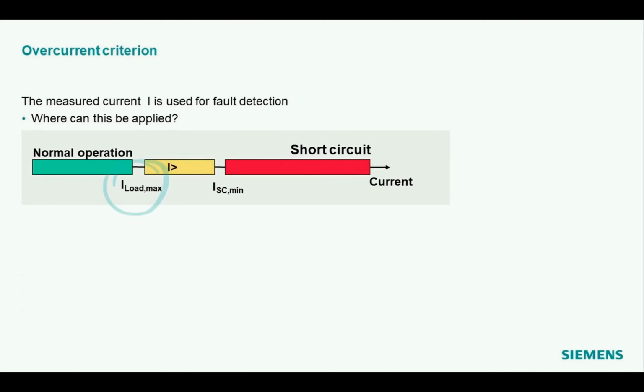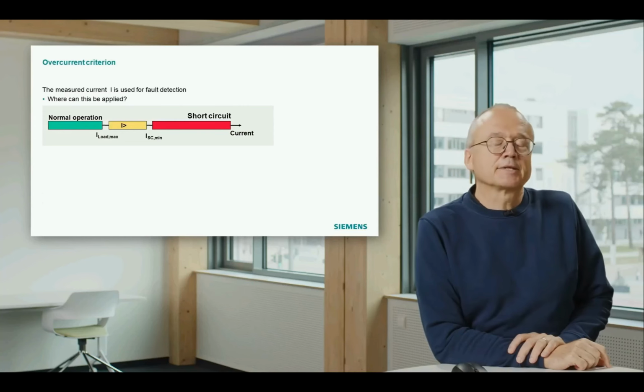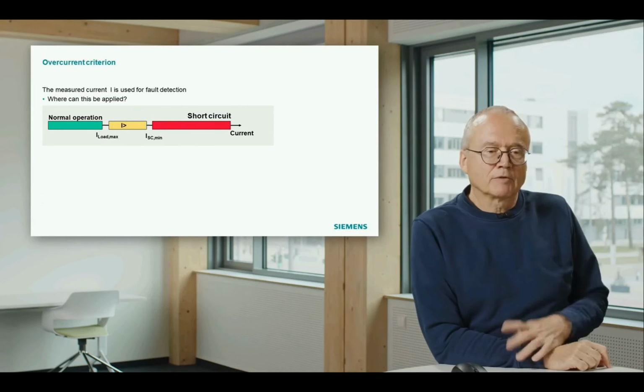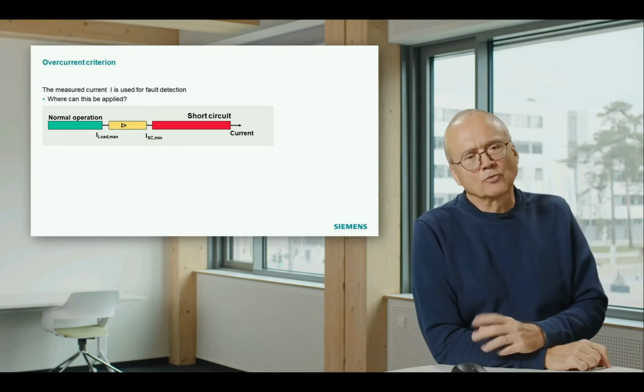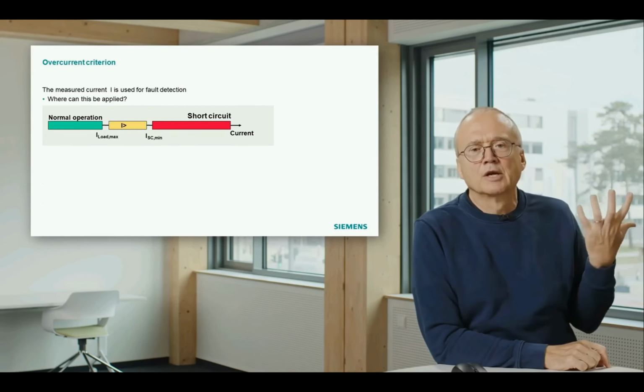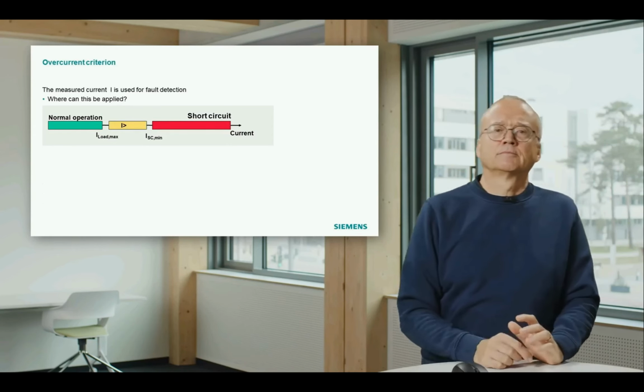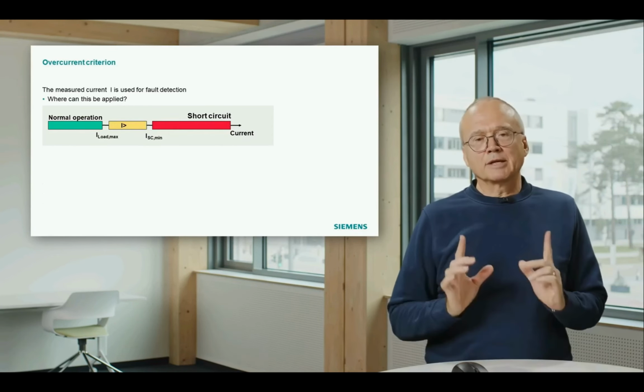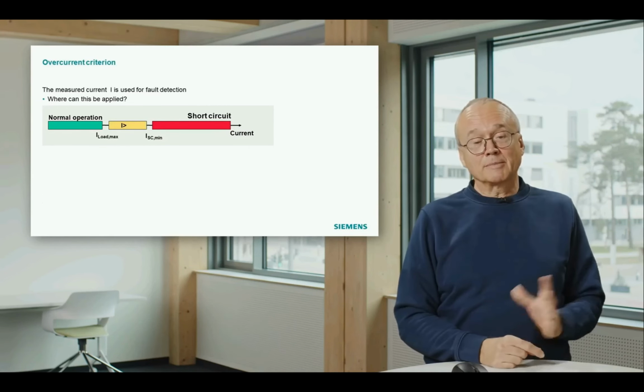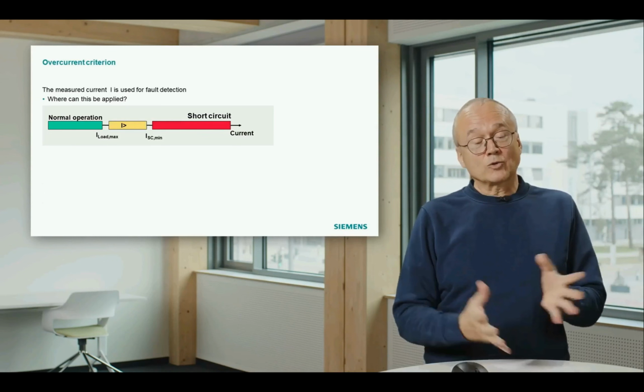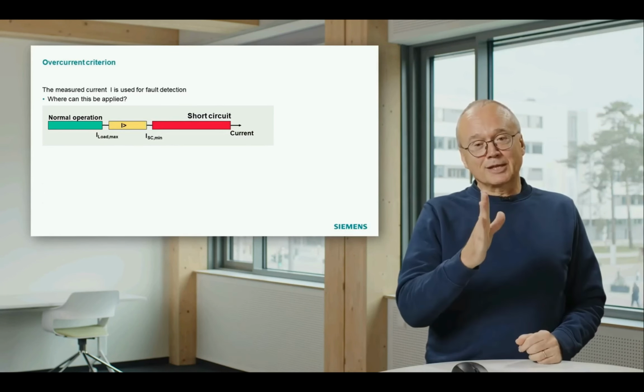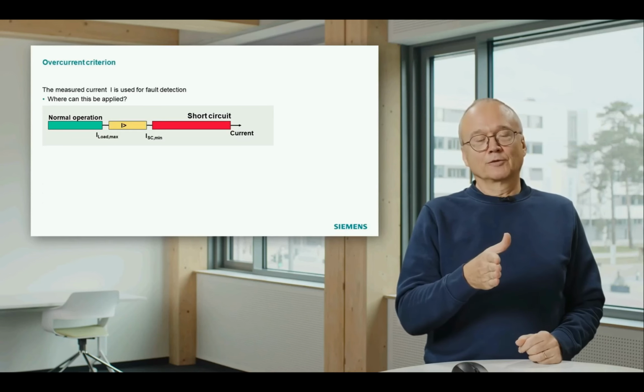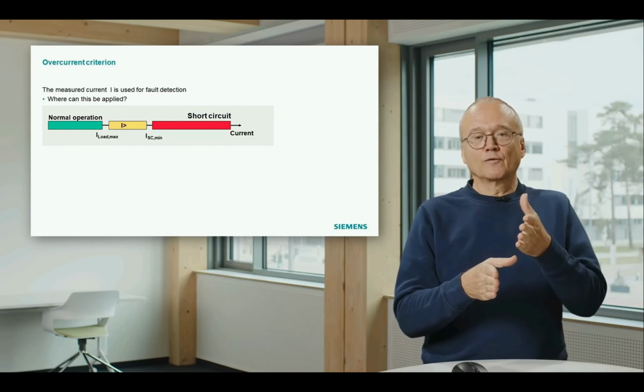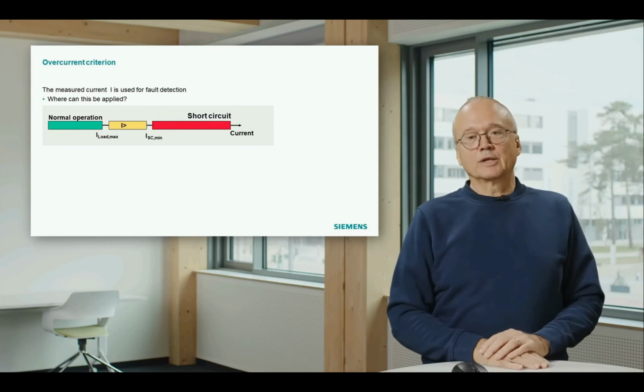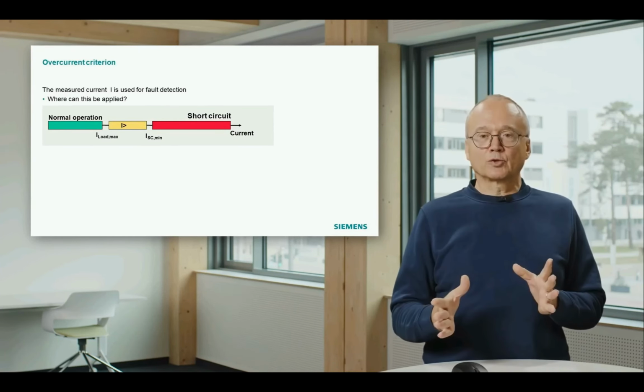An important thing in this context is, what is the maximum load current? And that is in many cases not so obvious. Imagine you are behind the transformer, then you can say, okay, the maximum load current is the nominal current of the transformer. But is that okay? Imagine you can overload a transformer. That means you can have cases where you have a short overload, and if you set your limit directly to the rated current of a transformer, as soon as we have a slight overload, our protection will see, oh, it looks like a short circuit, and will trip.